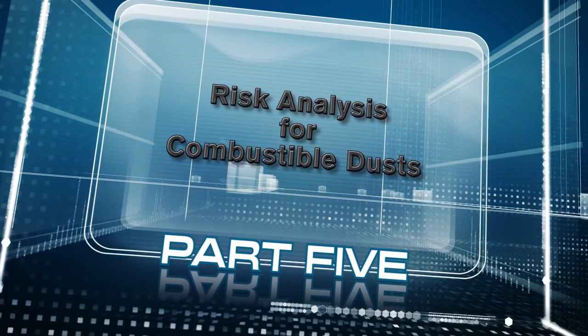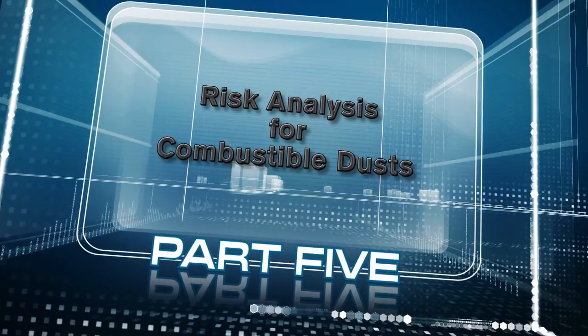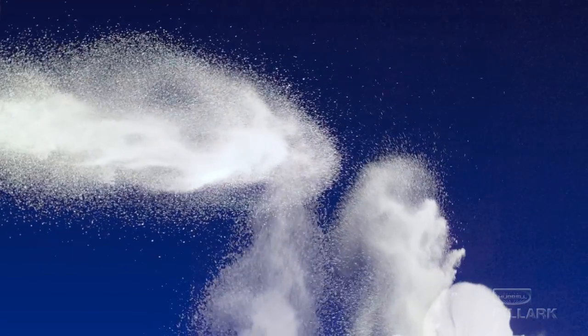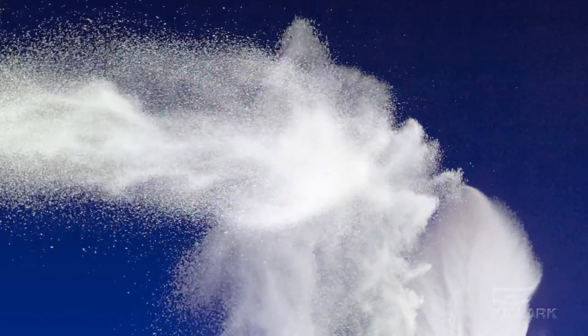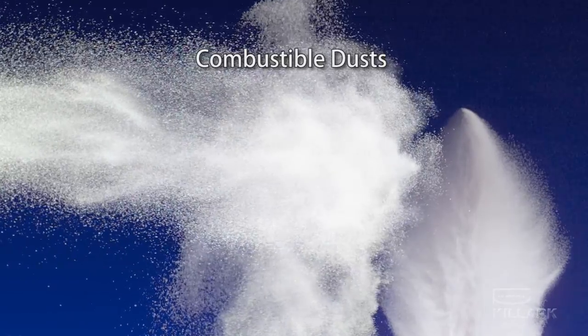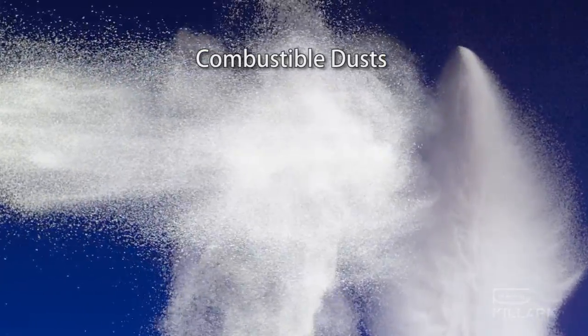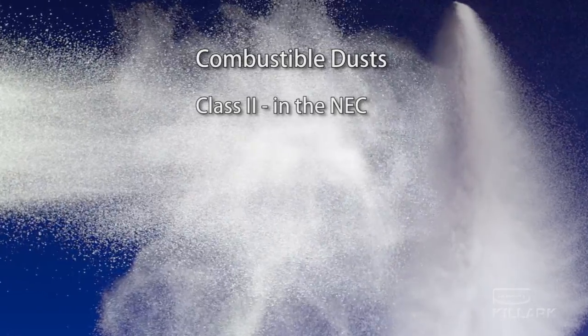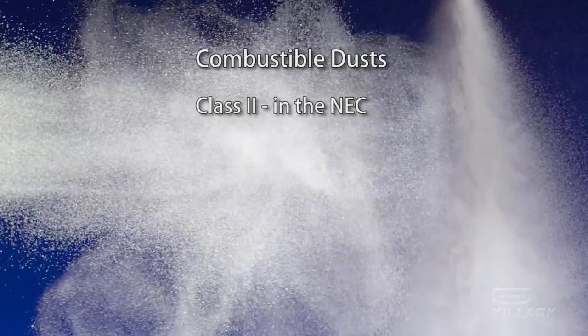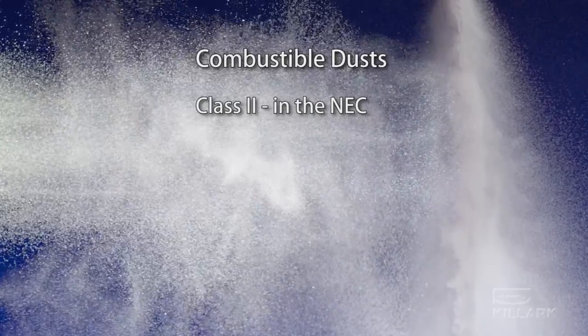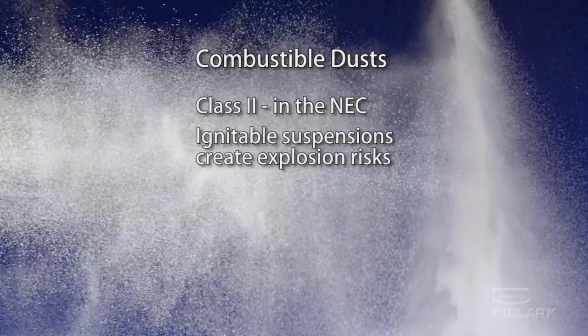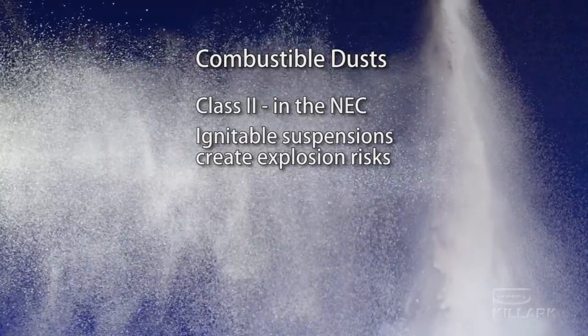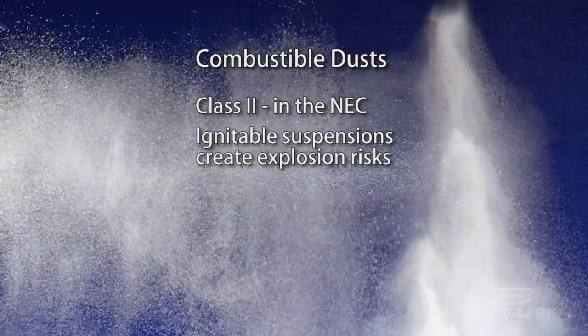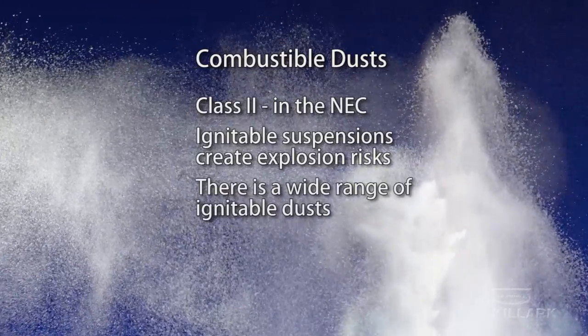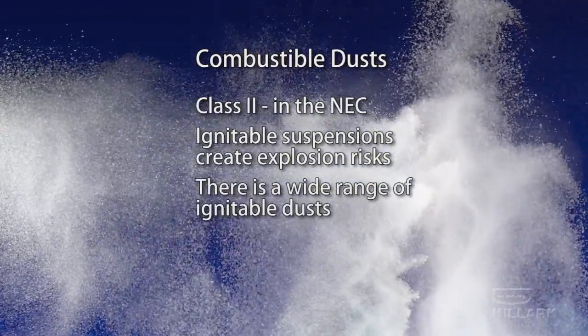Part 5. Risk Analysis for Combustible Dusts. Another class of risk requiring assessment for explosion potential is combustible dusts. Referred to as Class 2 in the North American approach, finely milled, ground, or pulverized organic material, like wheat, wood, and coal dusts, can be just as explosive as gases and vapors when suspended in the atmosphere. Certain inorganic materials, metal dusts, for example, could also form ignitable suspensions.